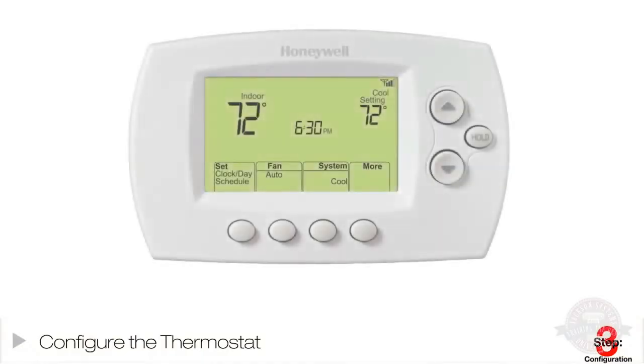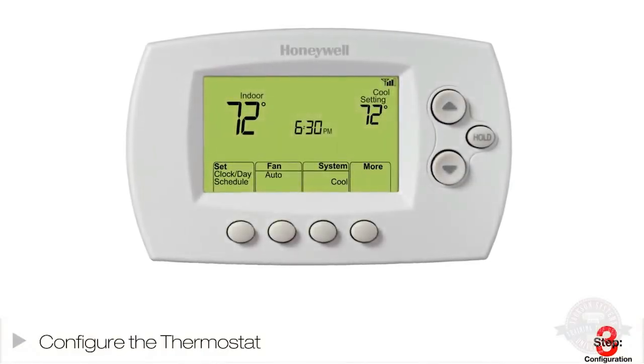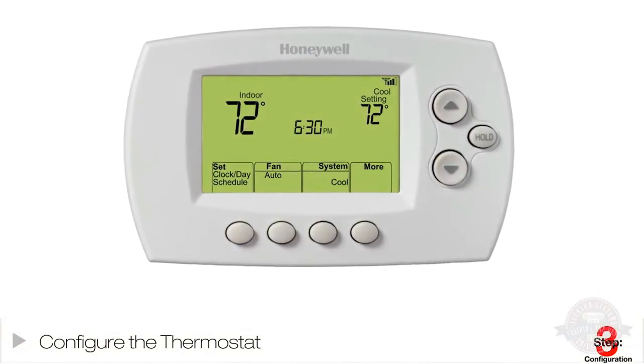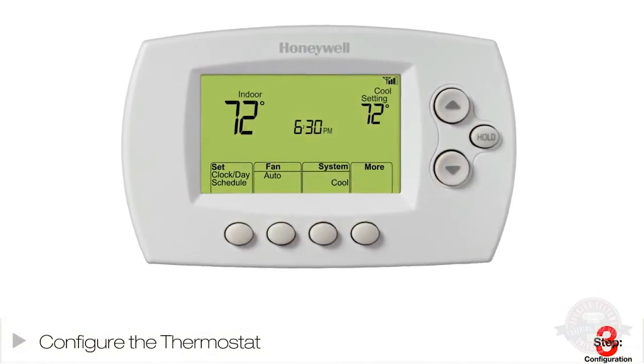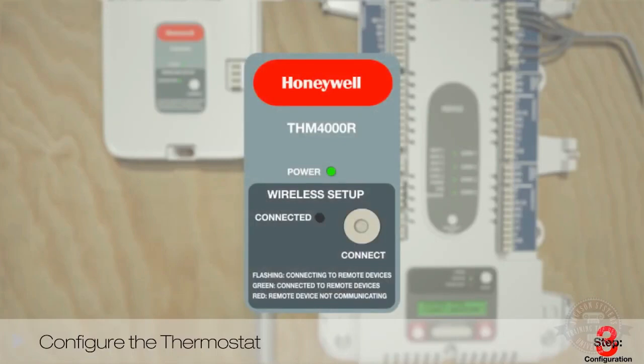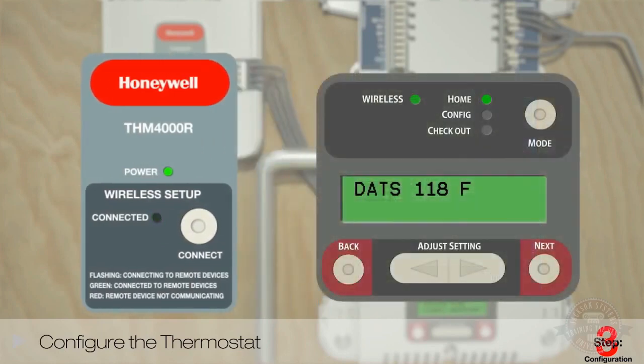It's time to configure the thermostats. If you're using a wired thermostat, complete the setup as if you were configuring a non-zoned home. If you're using a RedLink thermostat, push the button on the zone panel until the wireless LED lights up. This opens enrollment for all your RedLink devices. The green LED will flash on the RedLink adapter. That lets you know devices are ready to be enrolled in the system.